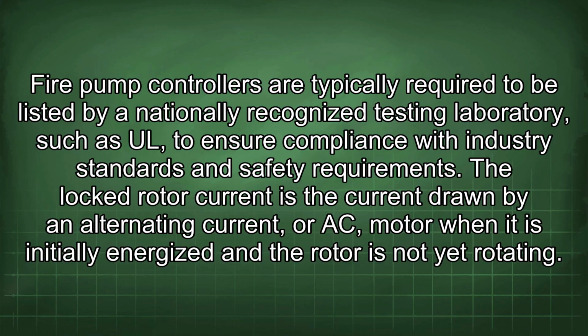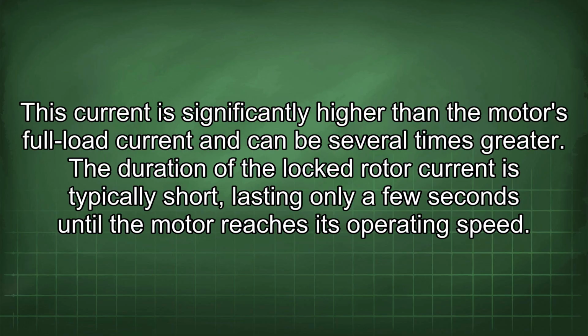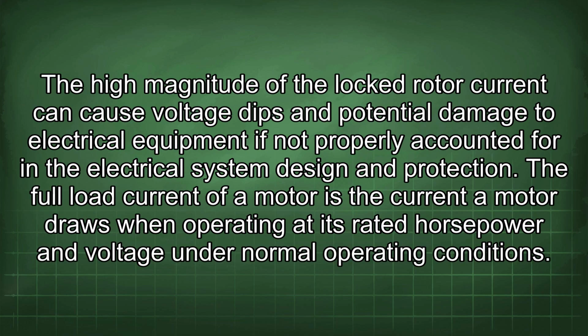The locked rotor current is the current drawn by an alternating current, or AC, motor when it is initially energized and the rotor is not yet rotating. This current is significantly higher than the motor's full load current and can be several times greater. The duration of the locked rotor current is typically short, lasting only a few seconds until the motor reaches its operating speed. The high magnitude of the locked rotor current can cause voltage dips and potential damage to electrical equipment if not properly accounted for in the electrical system design and protection.